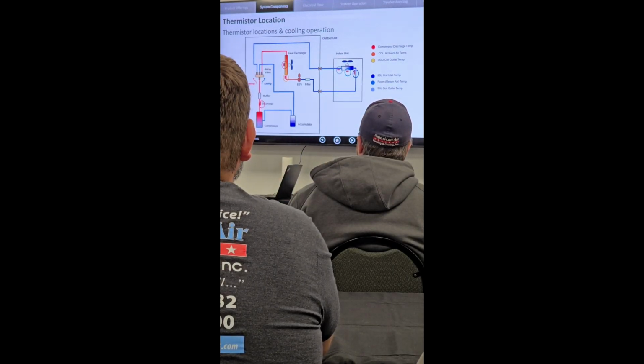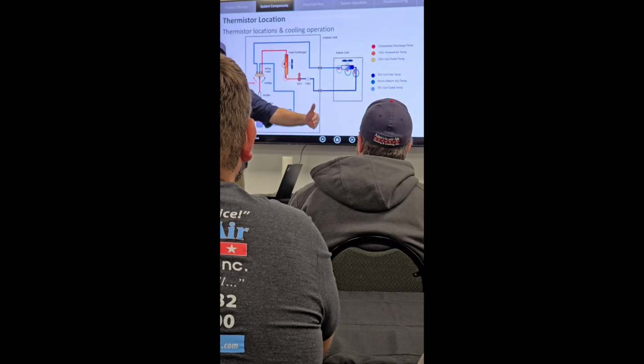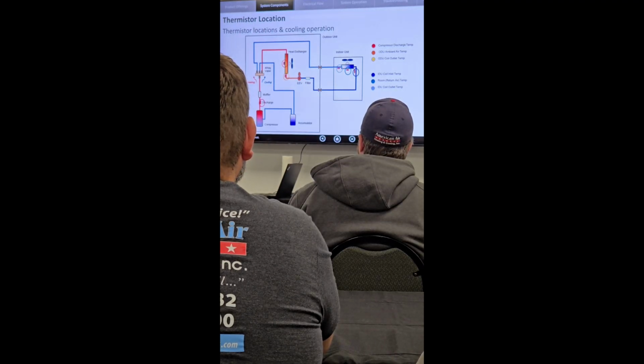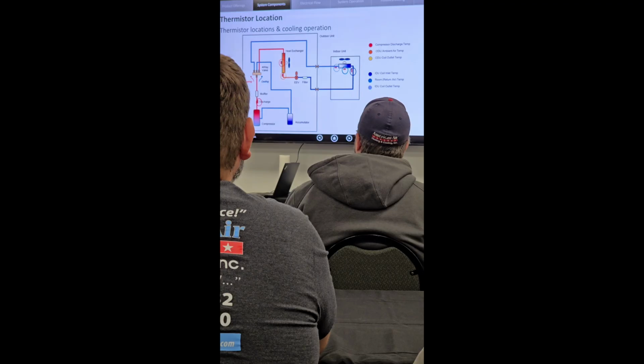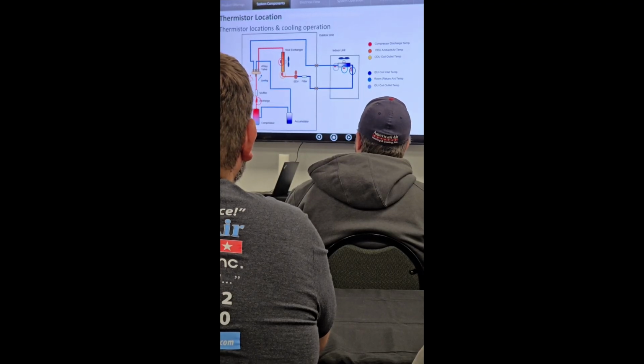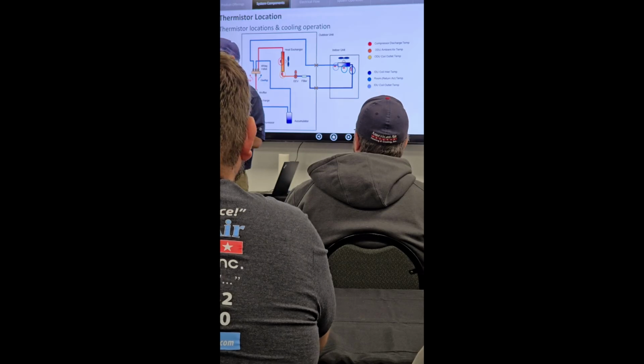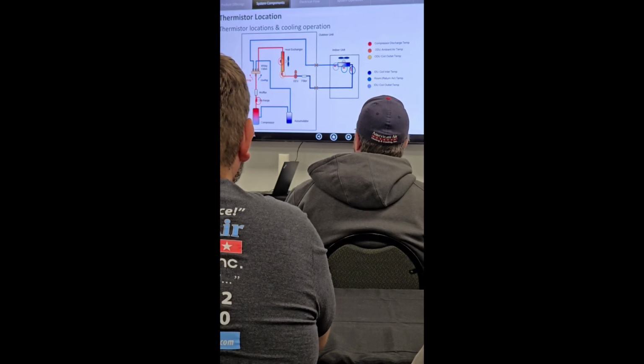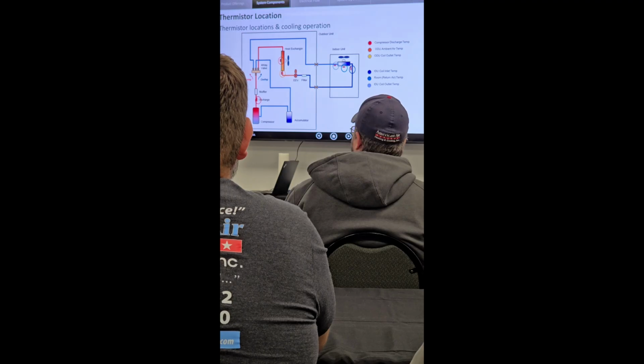The easiest solution is to just move the condenser down a little bit and run your line set that way. It doesn't look stupid, and it doesn't look like you bought a Mr. Cool. Because honestly, even though the IOM says you can do one loop, what's the next guy trying to impress the homeowner going to do? He's going to point it out and tell them it's wrong, even though it isn't. So my thing is, let's just move the condenser down and get that 9.6 feet I need, and be done with it. Not two loops or three loops, just one.